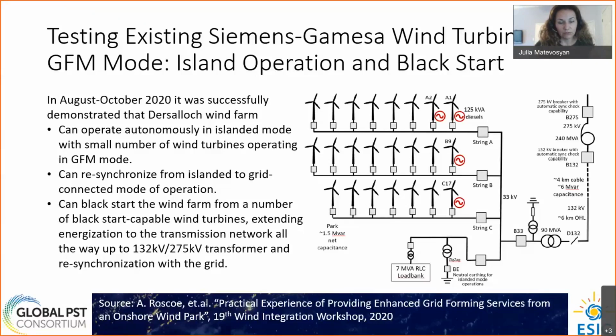They also used soft start, where voltage was gradually increased to reduce inrush currents. But they also found that because it's providing black start capability for the bigger island, and then eventually will power up the bigger portion of the grid, elements of the grid are exposed to lower voltages for longer times. And so that maybe is not a very useful strategy. They tried a different strategy where a bigger number of wind turbines were started simultaneously, and transformer tap changers were also used to gradually power up the rest of the grid, and this way provide the inrush currents that were needed by transformers.